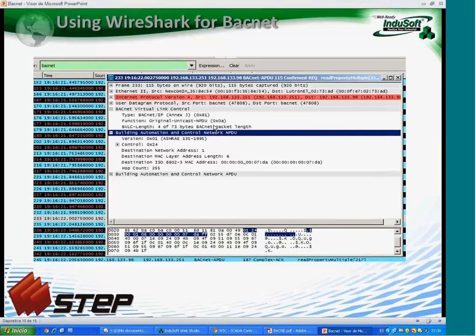What you should do in this case, if you don't have a CAS BACnet browser but you have the software you get from the manufacturer, is use this software to contact the device and see the information you need, and run Wireshark.